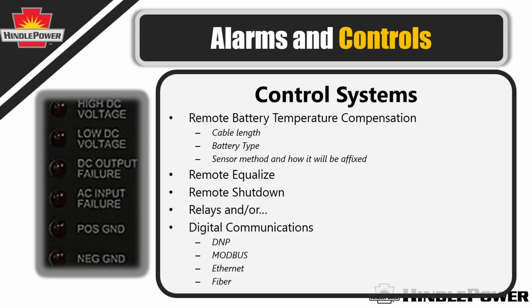Some of the other things that sometimes people think about is the ability to equalize remotely, or even more importantly, a remote shutdown, which could be used for any one of a number of reasons, including high voltage, high temperature, lack of ventilation, high hydrogen. So any one of a number of things could trigger a remote shutdown. And then various relays that would actually give you a relay closure for all of this.